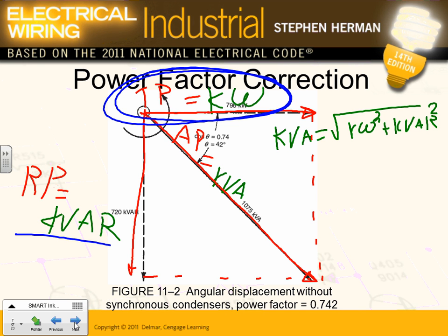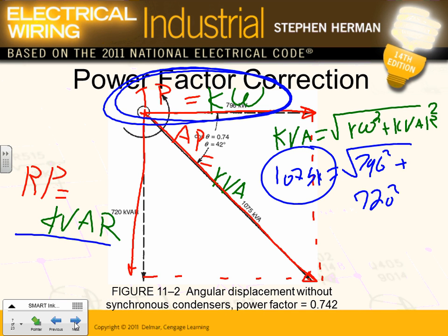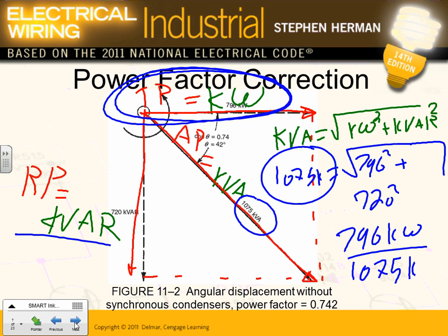Okay, so if you guys look at this example that they're giving, they have 1075 kVA. If you square the 796 plus the, what was that, 720 squared, you're going to get this value. So we have 796 kilowatt true power and 720 kvar. To find the kVA, you have to square them and take the square root of the two. You get 1075 kVA. If you take the 796 kW, divide it by the 1075 kVA, that will get you my power factor. And they have it here. Where's the power factor? Somewhere here. And that's the number 0.74. Now you take this 0.74 to town and you get penalized. If that's your building, you're screwed up. You're going to get penalized financially for this low power factor.